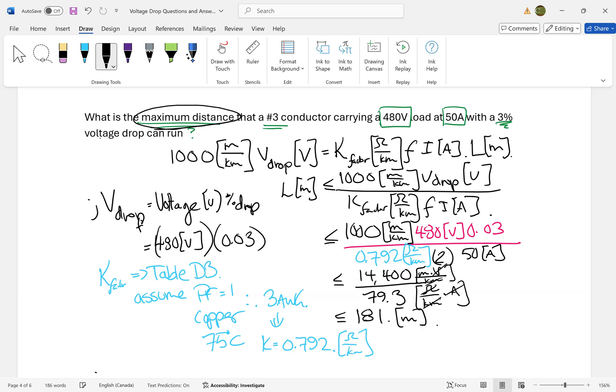181 meters is the maximum length that this #3 conductor carrying 480 volts at 50 amps with a 3% voltage drop can run. Hopefully that's helpful. If it is, please like, let me know what you liked or didn't like, and follow for more example problems as you study the Canadian Electrical Code. Thank you!